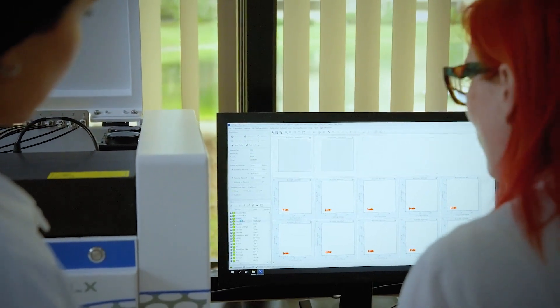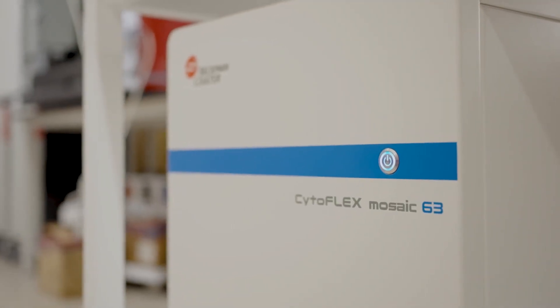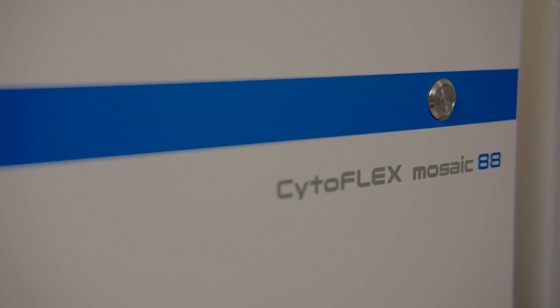But how can you ensure that your data is accurate? The CytoFlex Mosaic detection module has several advantages that help you check your data quality. From the capacity to choose the complexity you need and customizable unmixing options, the CytoFlex Mosaic is your path to elevating and adapting your conventional flow cytometry panels into the spectral domain. The CytoFlex Mosaic Spectral Detection module is available in two configurations: Mosaic 63, compatible with CytoFlex S4 lasers, and Mosaic 88, compatible with your CytoFlex LX. This way, you can choose the model that best fits your needs and your resources, making spectral more accessible.